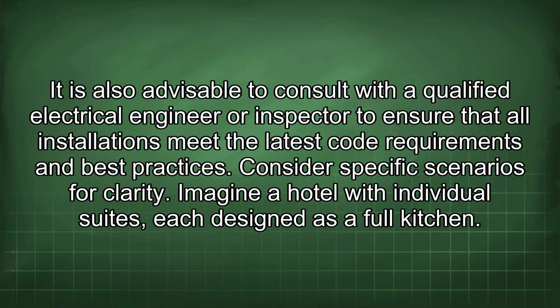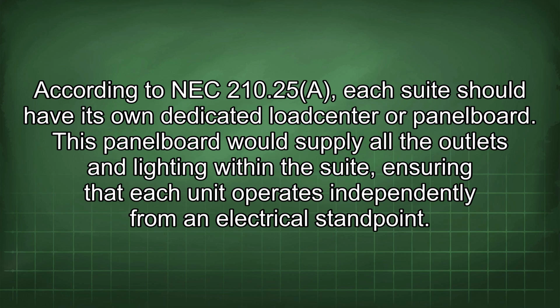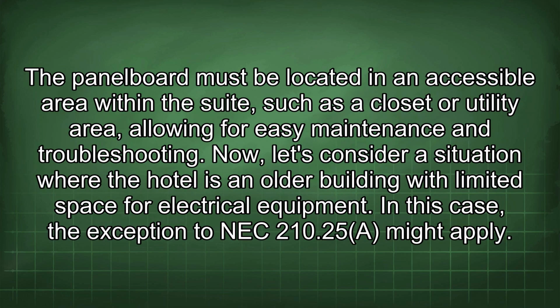Imagine a hotel with individual suites, each designed as a full kitchen. According to NEC 210.25(a), each suite should have its own dedicated load center or panel board. This panel board would supply all the outlets and lighting within the suite, ensuring that each unit operates independently from an electrical standpoint. The panel board must be located in an accessible area within the suite, such as a closet or utility area, allowing for easy maintenance and troubleshooting.